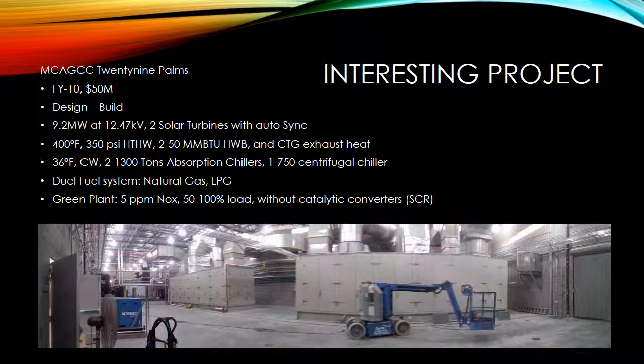These turbines can be swing loaded from 50% to 100% load, depending on the load condition on the base. And they only produce 5 parts per million of NOx from 50% to 100% loading, which makes them one of the cleanest turbines that you can find on the market without an after-stack catalytic converter. The turbine model is Mercury 50. You can look at them on the Solar Turbines website. They're very impressive machines indeed. Well, enough of that.